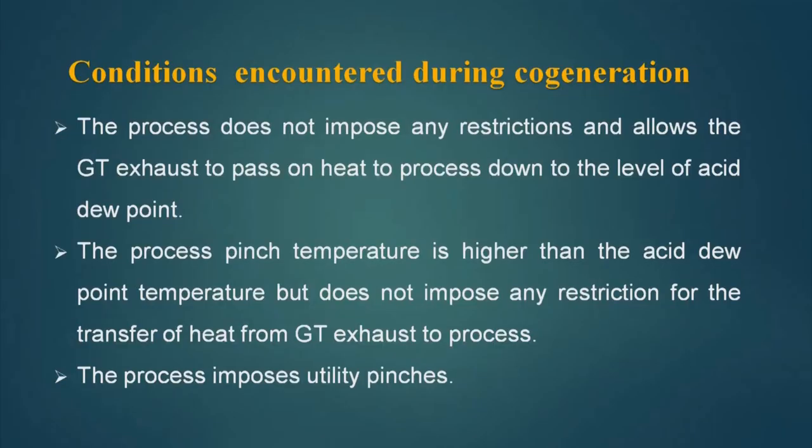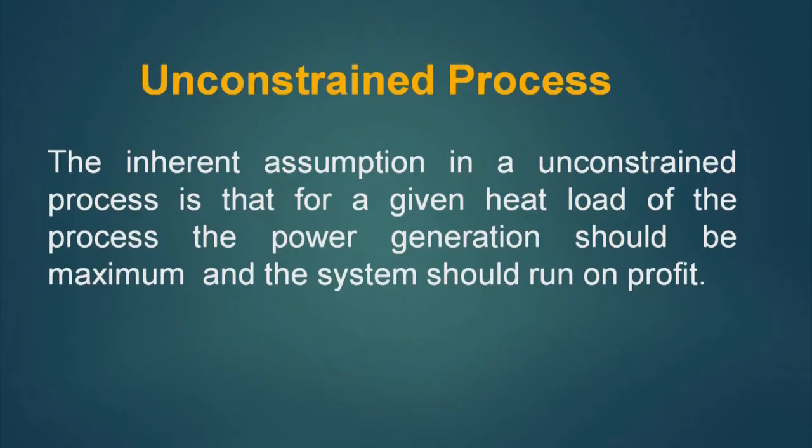The third is that the process imposes utility pinches. If utility pinches are there, then reaching to the acid dew point becomes difficult, the design becomes complicated, and there is a large loss from the system. Now, the first one is called an unconstrained process. The inherent assumption in an unconstrained process is that for a given heat load of the process, the power generation should be maximum and the system should run on profit.